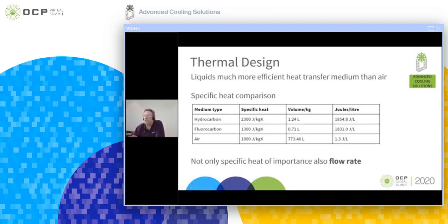And to show how these liquids are all similar across the board, I've chosen to show here a table representing the specific heat comparison of the different liquids. So the two most predominant liquids are hydrocarbons and fluorocarbons, and there's a significant difference in specific heat. However, the volume of liquid per kilogram is also very different, whereas the hydrocarbon has a much lower density than fluorocarbon does, which means that if you compare the amount of joules that can be transported per liter, these liquids perform almost identical when it comes to their heat capacity capability. And not only specific heat here is relevant, because flow rate is as well. And that combination is what gives you a good indication of what liquids can do.